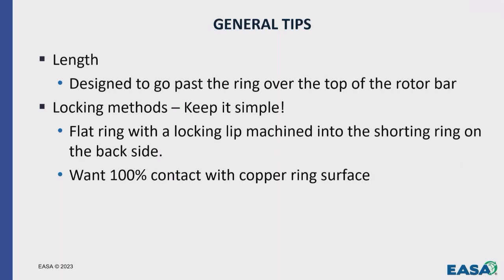So the best thing to do, when you make a stainless steel ring, is to keep it flat. No shoulders, just a good solid contact all the way around the ring. What that'll do is give you an equal compression force, and you'll end up with a lot better product in the end. You can lock the ring in by just a really simple method. You're putting it on your copper shorting ring. All you gotta do is just leave a little step on the outside of your copper shorting ring. We usually go about 25 high by 100 wide.